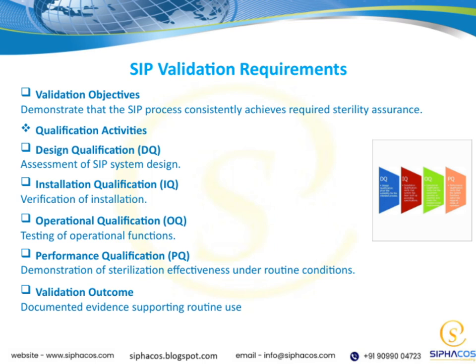To do this, we follow a series of qualification steps. First, design qualification checks that the system is designed properly. Then, installation qualification confirms everything is set up correctly. Operational qualification tests that the system functions as expected. Finally, performance qualification shows the sterilization works consistently in real-world conditions. Together, these steps provide the documented proof we need for routine use.